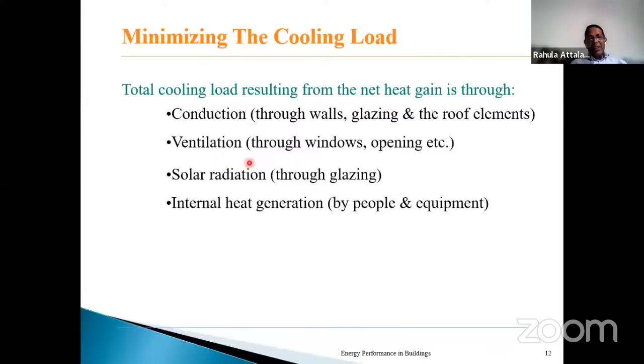So then air exchange will take place. But if it is involuntary, then we call it infiltration, not exactly ventilation. Ventilation is the air that is required, deliberately and purposefully brought into the building. It's mainly to control the air quality inside the building, with the health requirement. Then the third is the solar radiation. The first two are related to the immediate surroundings, the outside conditions: temperature and air movement. The third is coming from the sun, and it enters the building through the glazing, that is the transparent part of the walls or the windows.